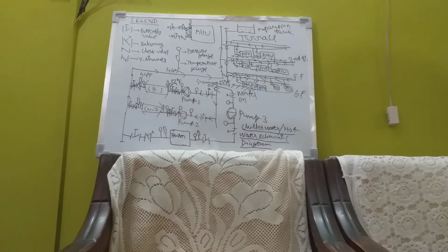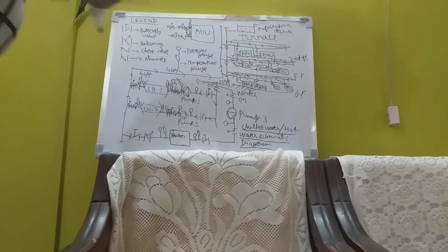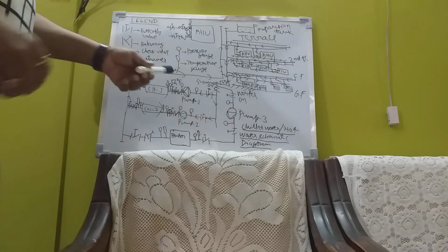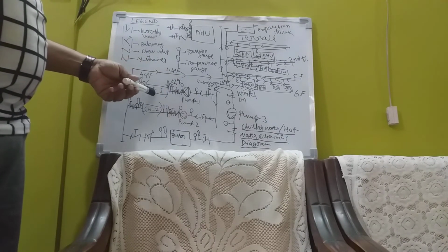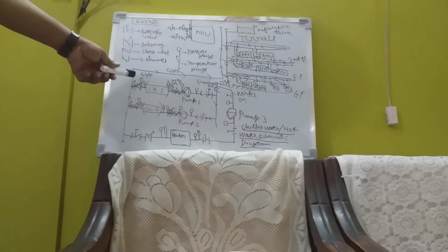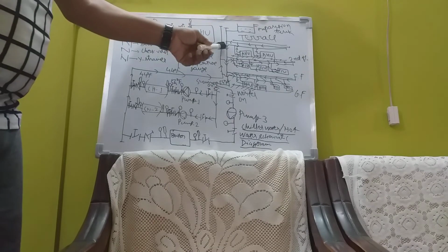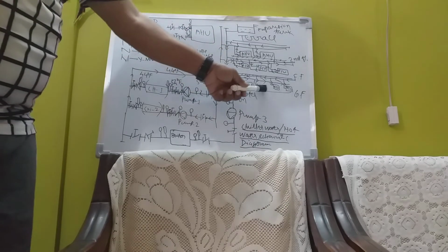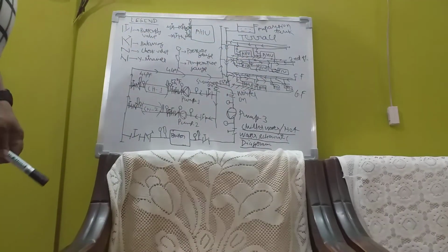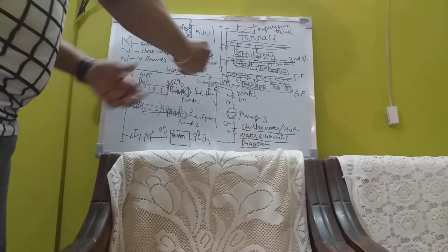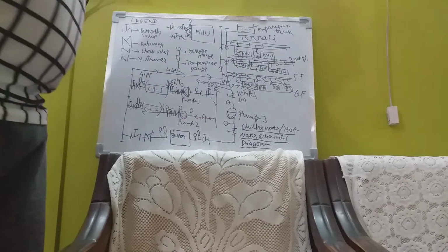Now, what happens? The chiller pumps the water at 54 degrees Fahrenheit to the chilling machine. It gets cooled to 44 degrees Fahrenheit. The 44 degree Fahrenheit water comes through this path, and from here it supplies to different AHUs and FCUs. You can see the diagram. See the direction of the arrow marks. The water is flowing like this and supplying to the AHUs and then the FCUs.